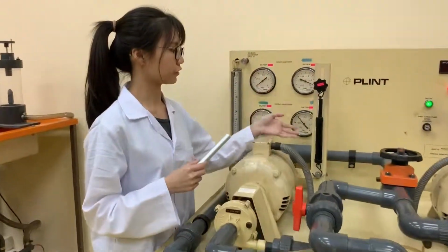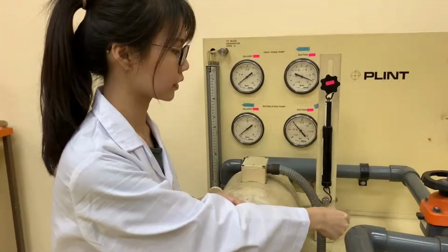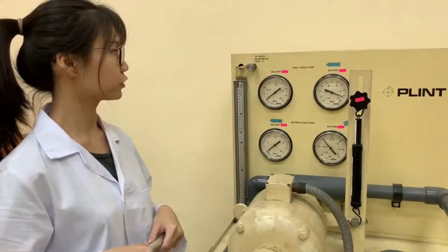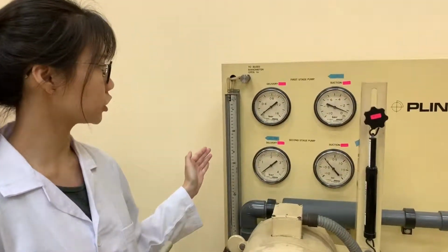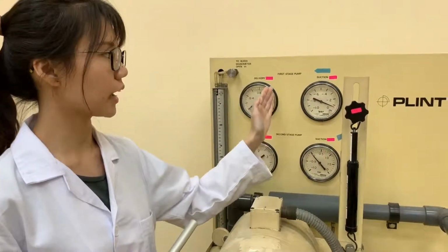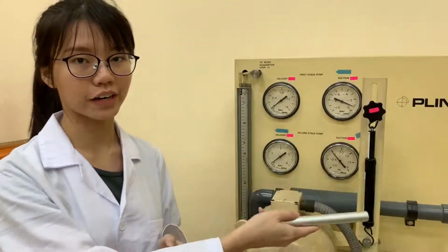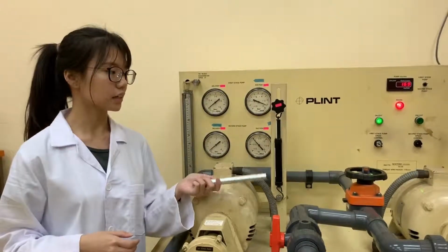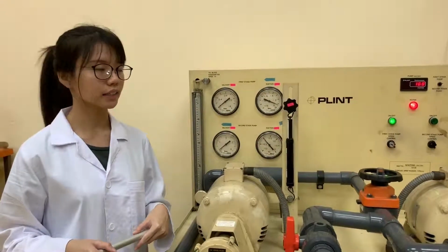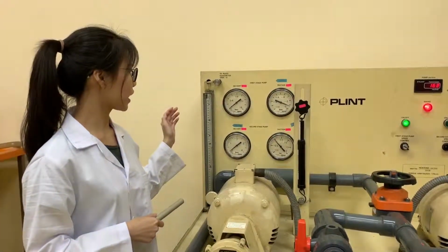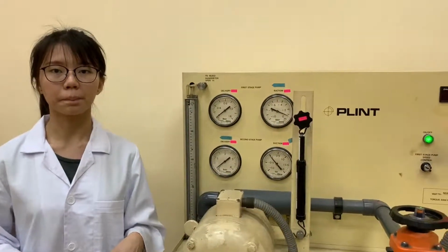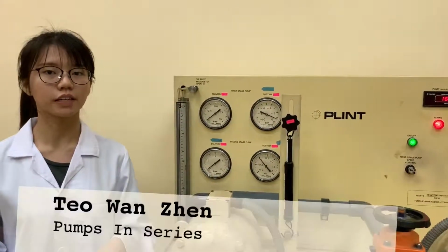We have to adjust the force until it's parallel to the beam and note down the force. Meanwhile, we have to record the pump head, delivery pressure D1, and suction pressure S1 with the maximum flow rate. Next, adjust the control valve to change the flow rate and take 5 different readings at different flow rates. Repeat the steps for the pump at a speed of 3000 rpm.